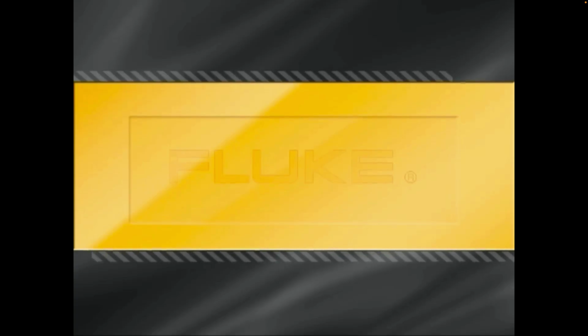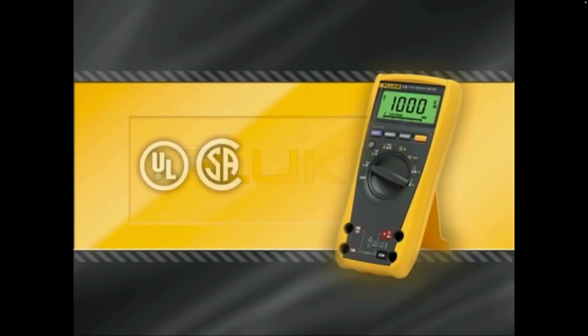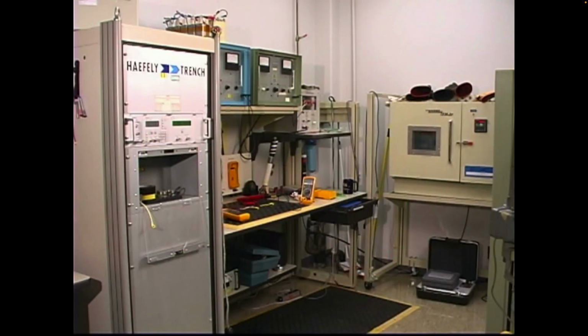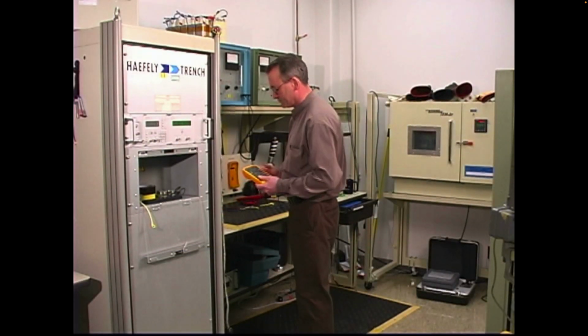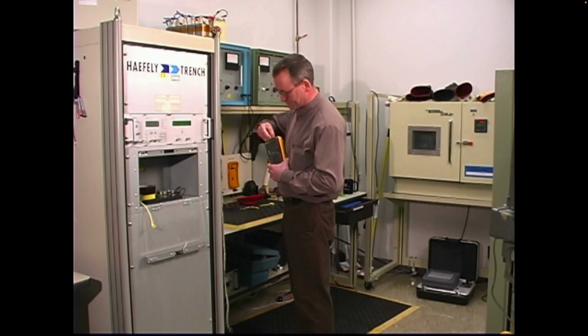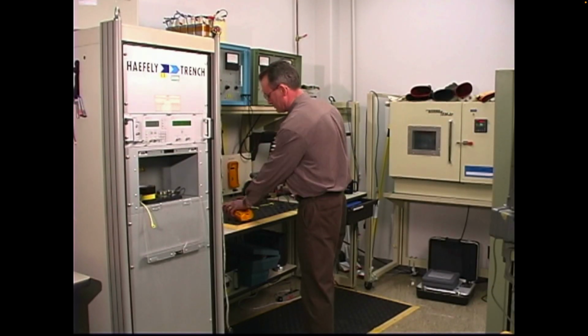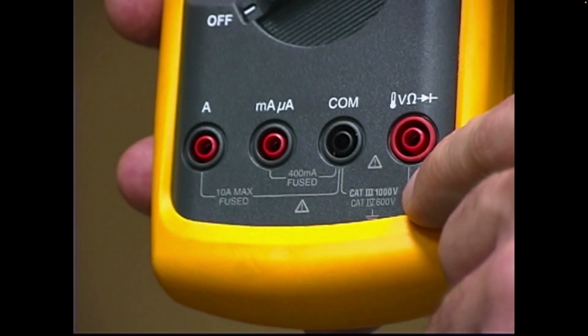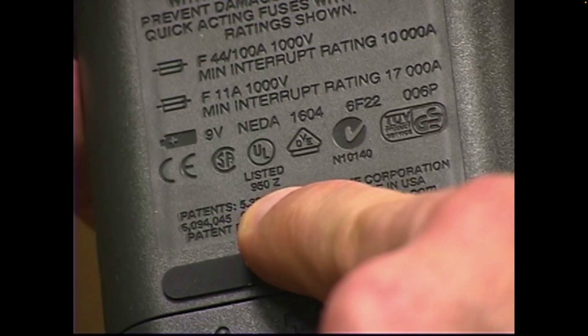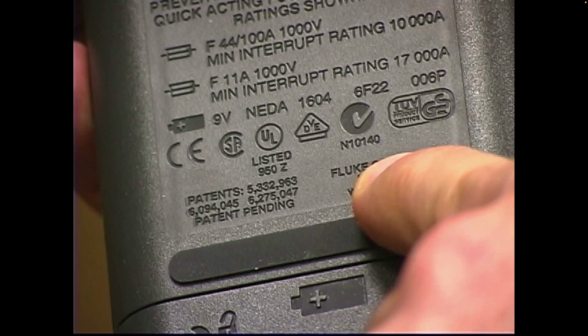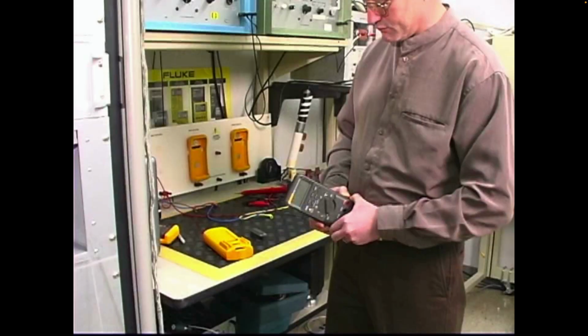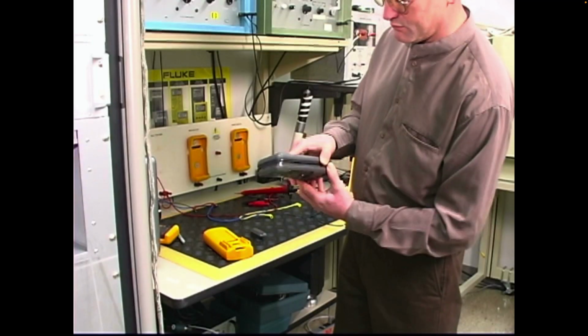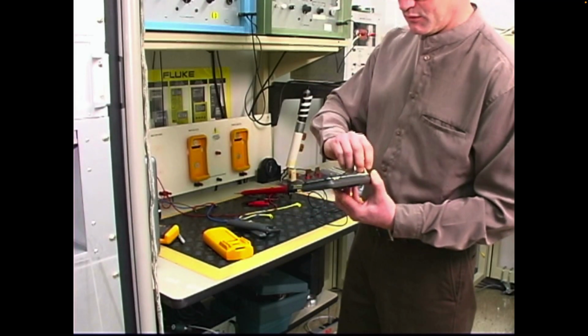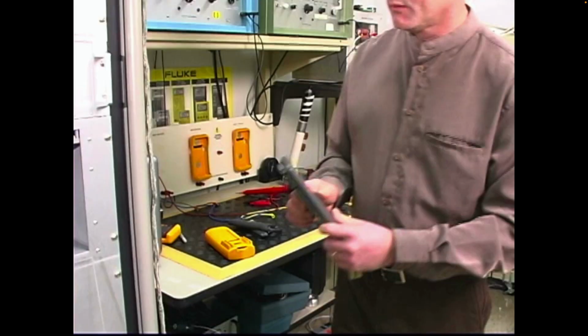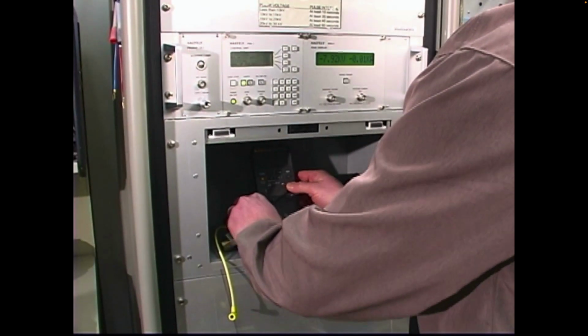Meters and other electrical test tools should be independently evaluated to make sure they can survive high voltage transients. A special test machine is used to generate the overvoltage transient and fault current as defined by national and international standards. This meter is marked 1000 volts Cat 3 on the front of the case. More importantly, it has been certified by an independent testing laboratory. A 1000 volt Category 3 tester is required to survive a minimum of 10 transients of both positive and negative 8000 volts without creating a hazard.